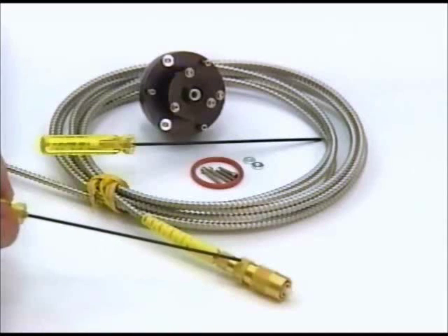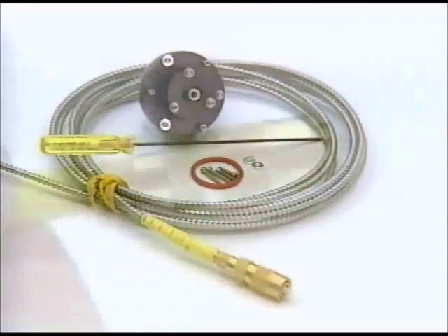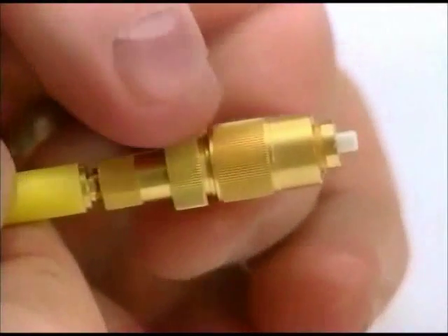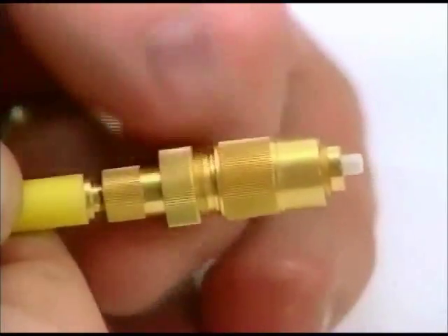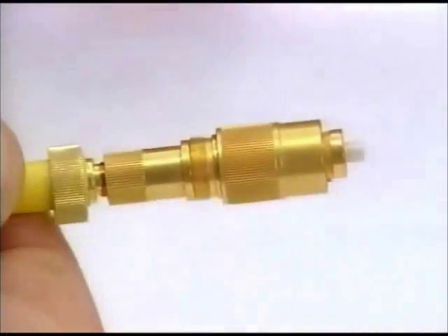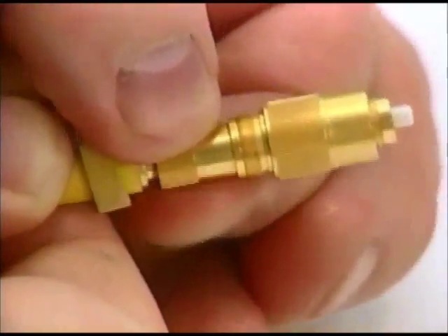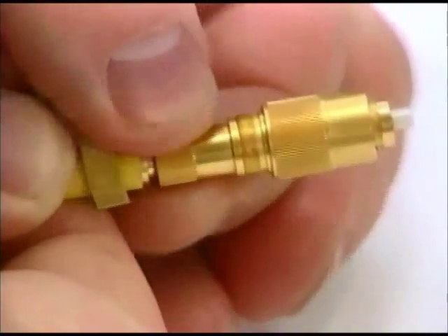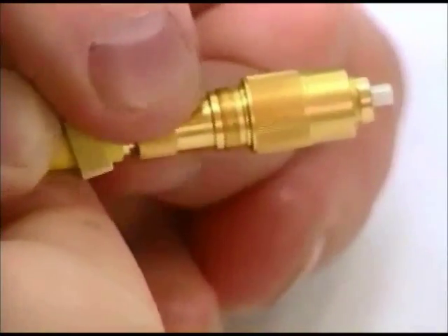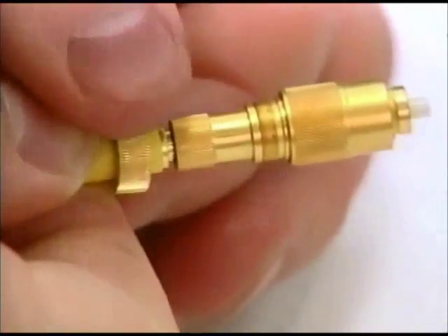There's a little ring on the back here called a locking ring, and there's a little adjustment screw on the back for adjusting the amount that the ferrule, the white part, actually sticks out. So if you loosen that locking nut and bring it back, by turning this section, you actually change the distance that the ferrule will stick out from the end of the connector, and that gives us our z-axis control.